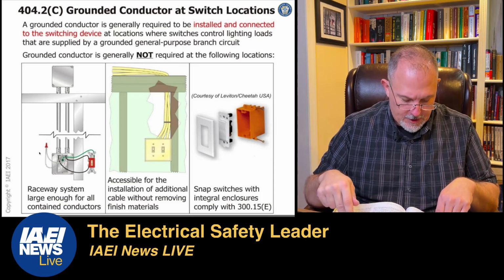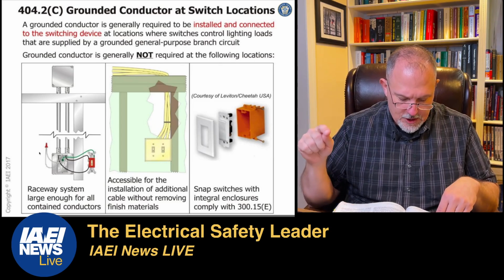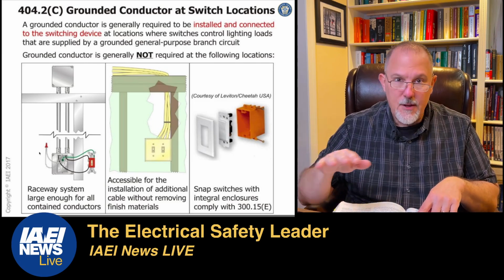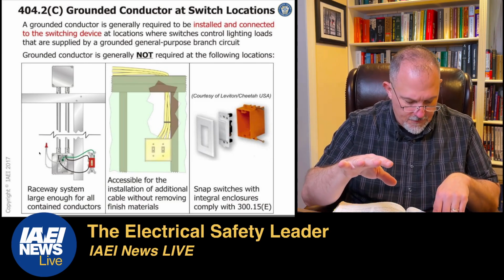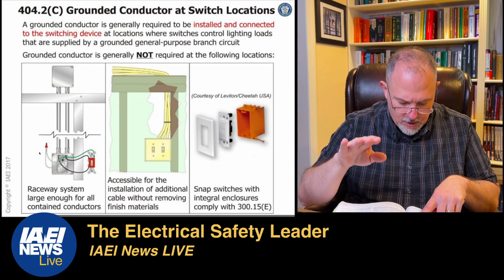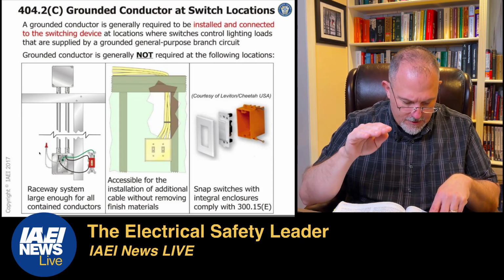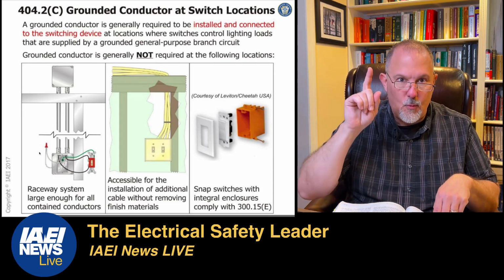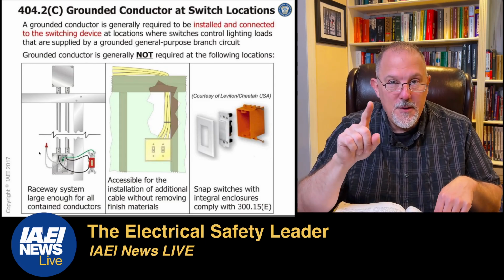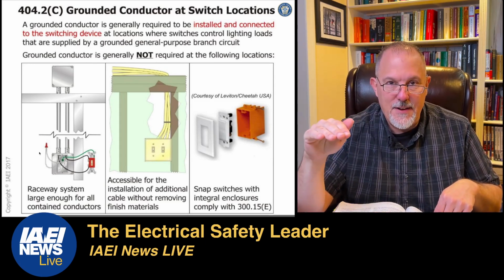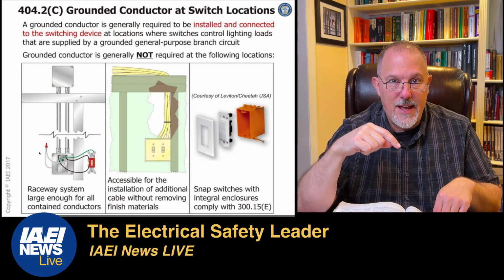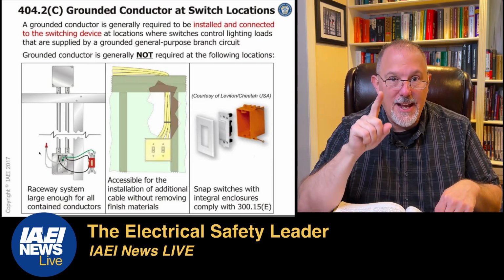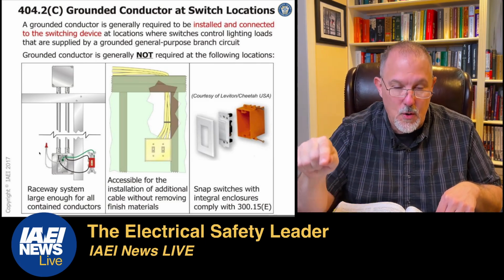the applicable building code, where multiple switch locations control the same lighting load such that the entire floor area, which is not new, of the room or space is visible from a single or combined switch location. The grounded circuit conductor shall only be required at one location. So remember before they said you didn't have to have it at all, but now they're saying you have to have it at least at one location, and it's going to be where you do the control.